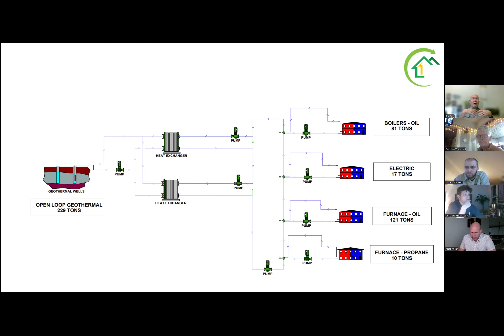That gives the big loop a chance to share energy between spaces. People often wonder, what if I'm down the road from the next house, who's taking all the heat out of the circuit? We can show in the models it doesn't make a dollar of difference in a year. As long as these heat pumps get above 25 to 30 degrees Fahrenheit, they'll operate at nearly the same efficiency as if they were getting 55 degrees, because there are plenty of BTUs in the water. It's just a matter of extracting it efficiently, which is what these heat pumps are designed to do.